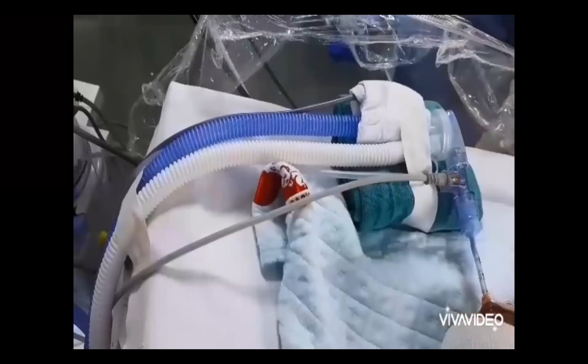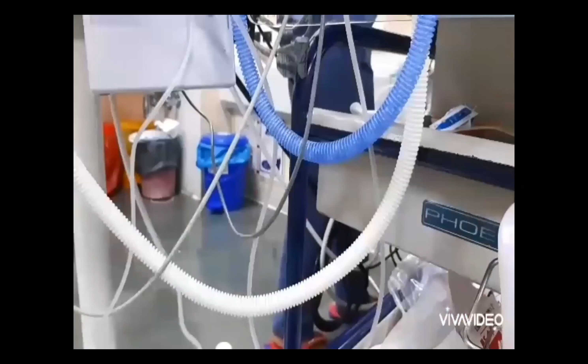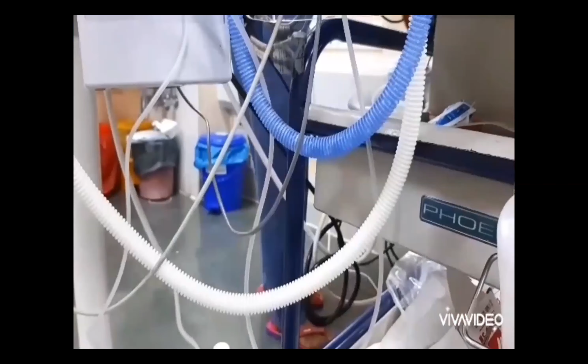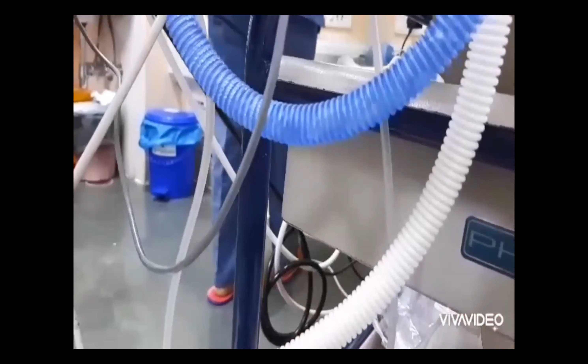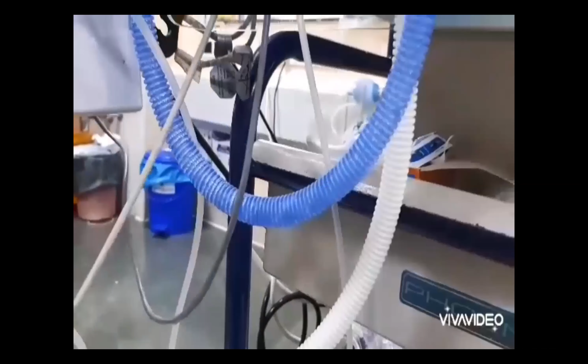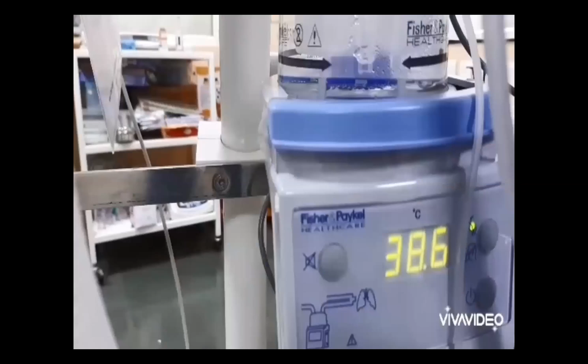And as we walk across, we see that there is water in the blue limb, which we see here. That is the inspiratory limb, and that is moving with the inspiration and expiration movement of gases, and this sets up auto triggering. That is, these are the false breaths. So that's why we see that the baby has a very high breath rate and the water level.